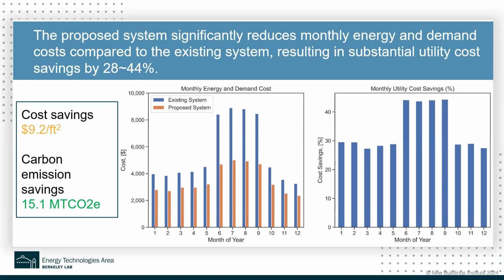And most important is the carbon emission savings. Since we utilize the CO2 storage tank to shift the on-peak electricity consumption, what we can call dirty electricity, to more green electricity during off hours, we can achieve about 15 metric tons of CO2 emissions savings. And overall, we have roughly 28 to 44% cost savings by installing this system in place of the existing one. We can test it out in the coming year, and we'll see how it comes out at the end. Thank you.